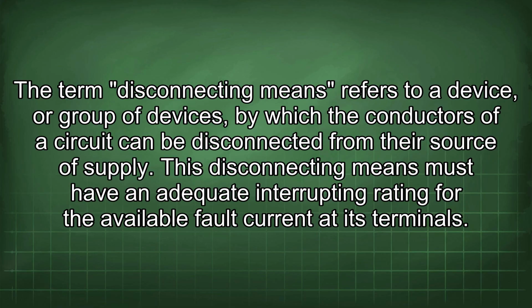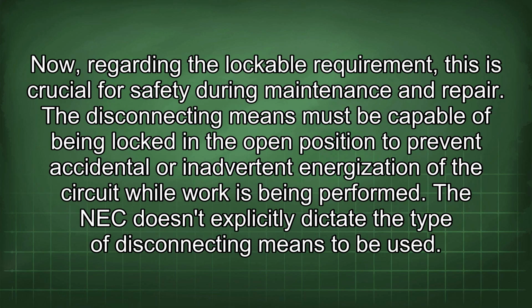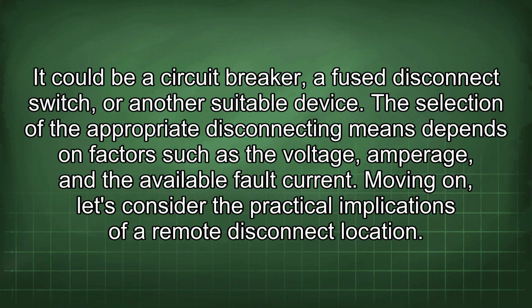This disconnecting means must have an adequate interrupting rating for the available fault current at its terminals. Now, regarding the lockable requirement, this is crucial for safety during maintenance and repair. The disconnecting means must be capable of being locked in the open position to prevent accidental or inadvertent energization of the circuit while work is being performed. The NEC doesn't explicitly dictate the type of disconnecting means to be used. It could be a circuit breaker, a fused disconnect switch, or another suitable device. The selection depends on factors such as the voltage, amperage, and the available fault current.